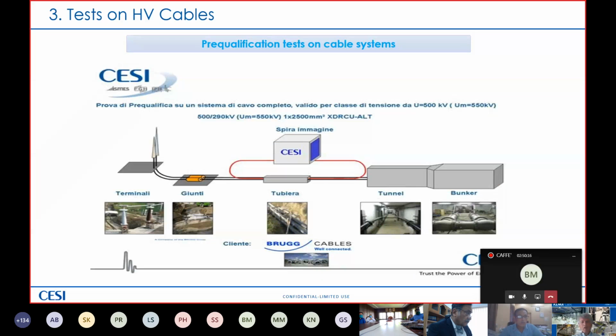Let me show this very important diagram to have a better understanding of a cable system situation. Let's start from the left. On the left, you have the cable termination. This is a platform that is put outside. You can see here that there are two different colors of cable termination. It's because I consider one porcelain, the light brown, and one gray for silicone. And this is normally the solution that cable manufacturers apply in order to qualify both solutions, because it means that during one test you can qualify different cable termination designs.